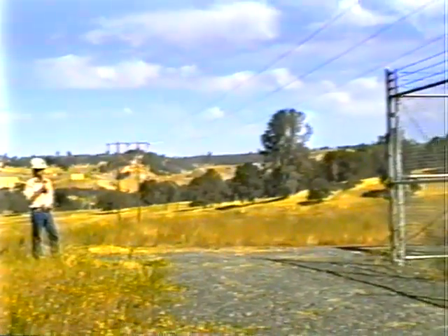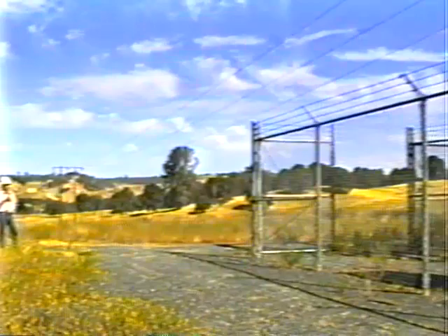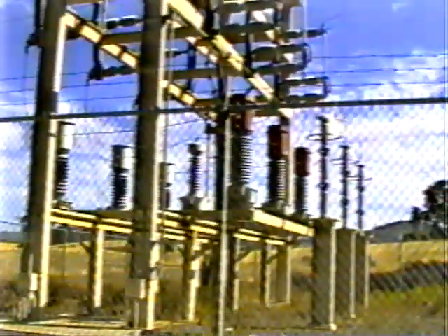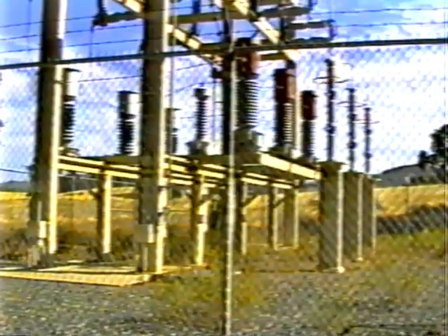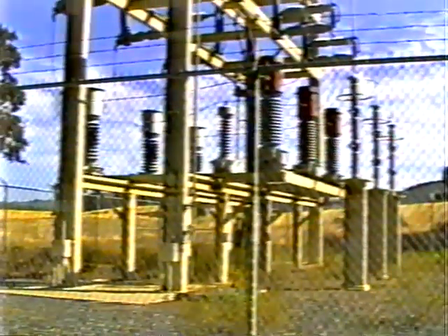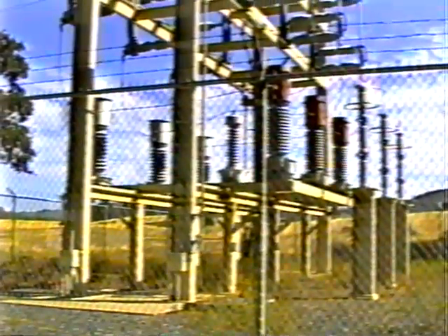Purpose of this substation is twofold. It provides all the metering services for our local utility company, PG&E, and it also provides protection because this is all 115 kV, and we have battery-operated switches that operate off of both manual controls and protective relays that are inside these enclosures over here.